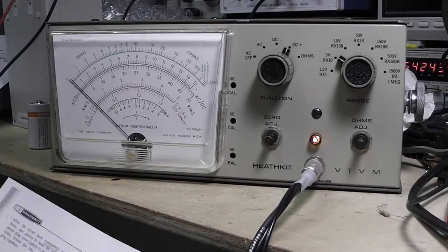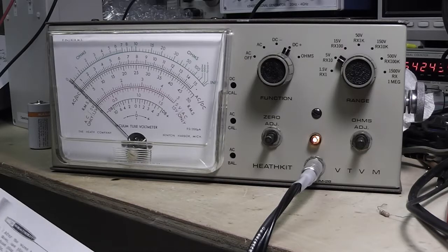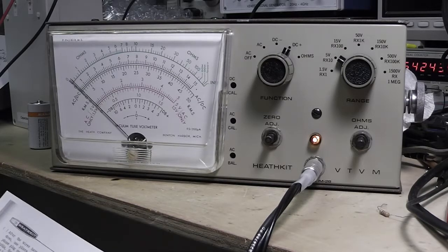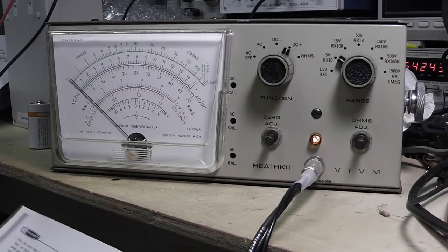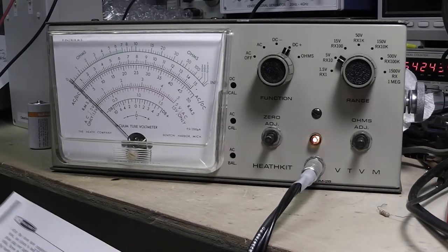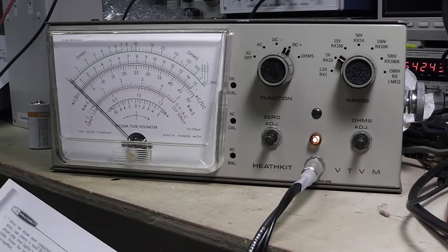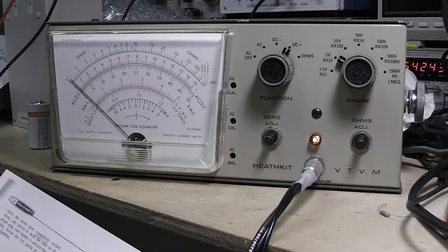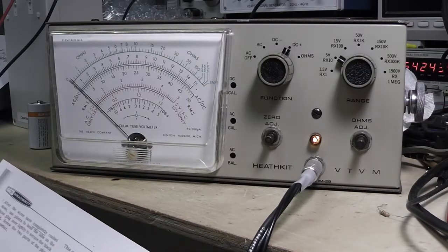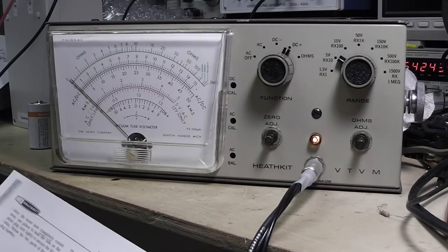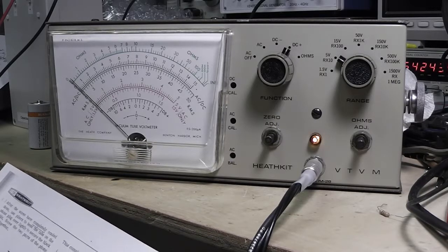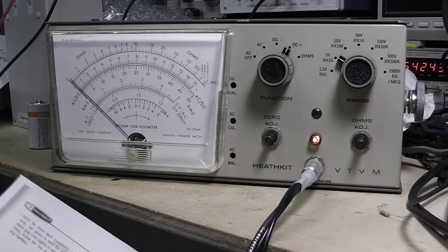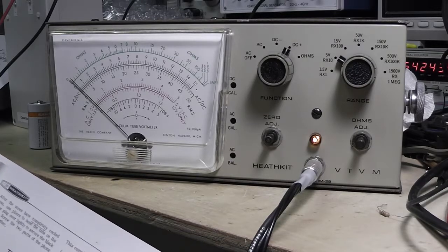So it says here, check operation of the 0 adjustment control. Turning this control should move the meter pointer part way up the scale. Set the pointer to 0 at the left side of the scale and check for 0 resting when the function switch is changed to DC minus. It should be possible to obtain a 0 adjustment control position that will keep the meter pointer stationary when switching from DC positive to DC negative.